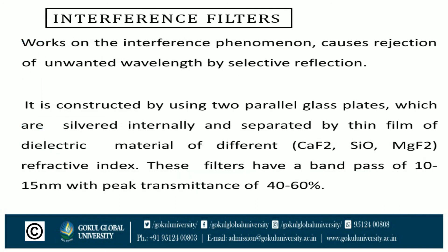Interference filters work on the interference phenomenon, causing rejection of unwanted wavelengths by selective reflection. They are constructed using two parallel glass plates that are silvered internally and separated by a thin film of dielectric material such as CaF₂, SiO, or magnesium fluoride.